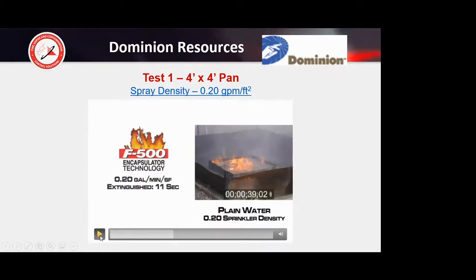Sometimes when people look at this, they go, oh, well, the foam can put this out, and they're 100% right, foam can put this out. It's just that foam can't operate on an under turbine lube oil spray fire. And so that's what we're trying to do, is compare the encapsulator agent to the water for this specific application.